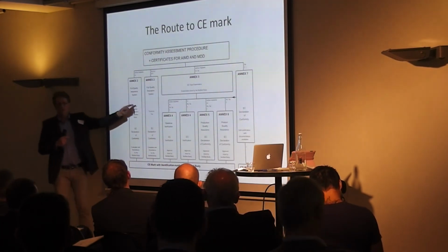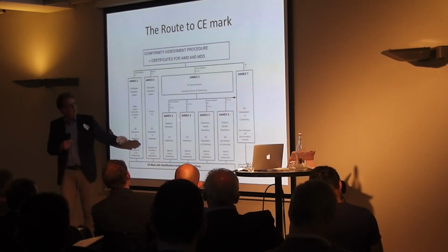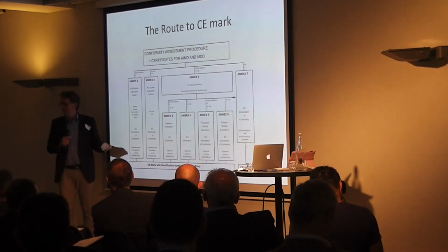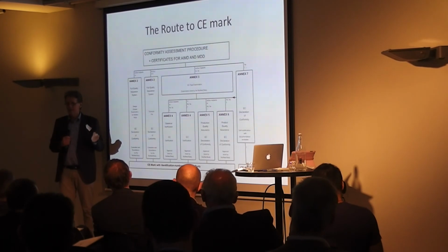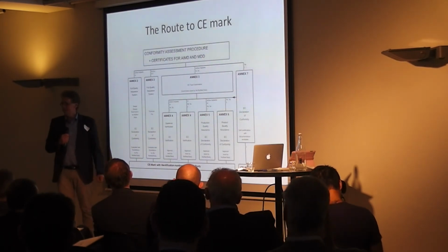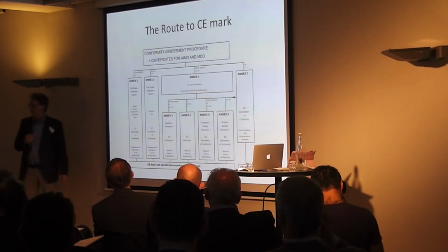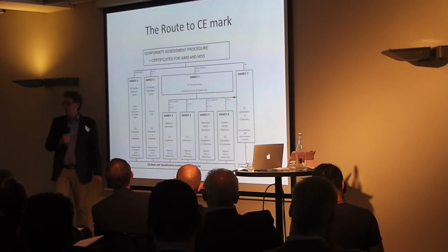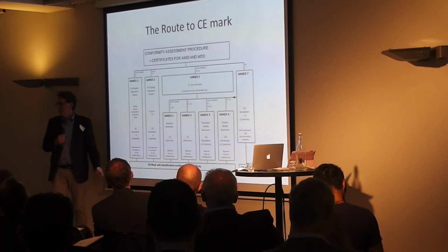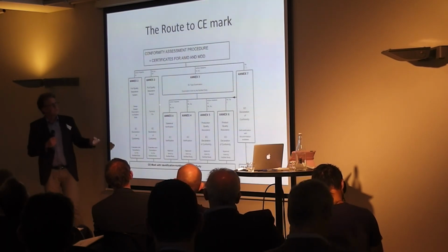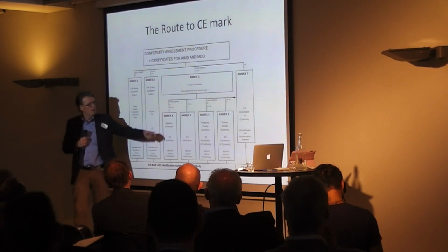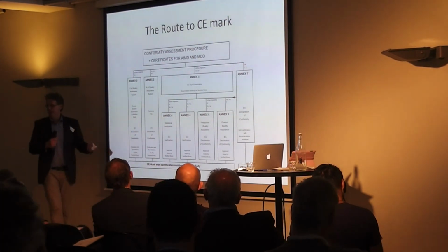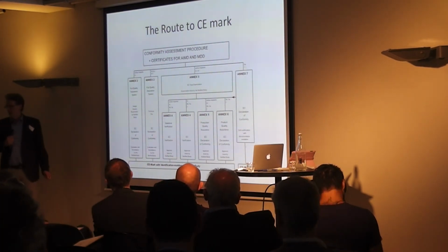That's process work. And these other annexes allow for type testing, so that you have your software ready and bring the software to a test house, to a notified body, and then they test your software. But what can they test? They can test your user experience. But can you really test the accuracy of the implementation of the software requirement specs? How to deal with it? So these are alternative ways for non-software applications, I think.